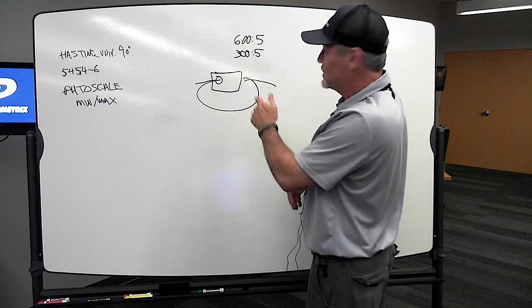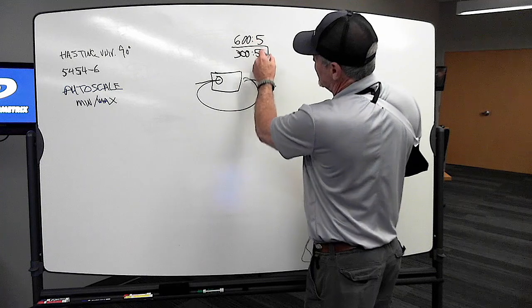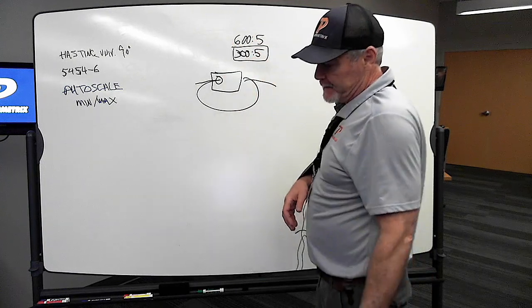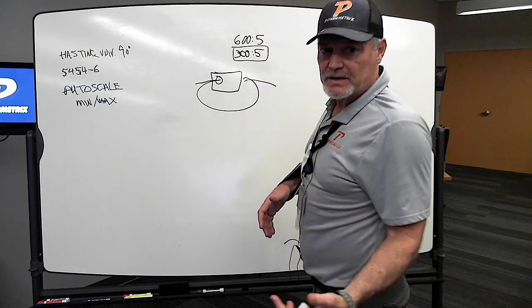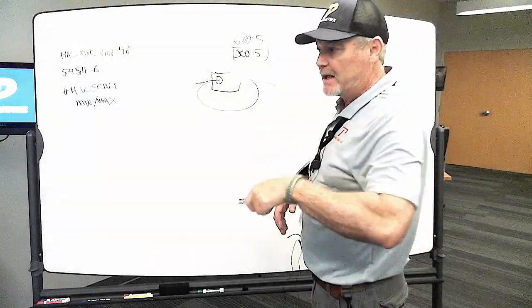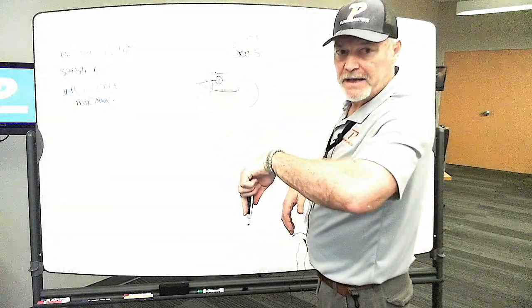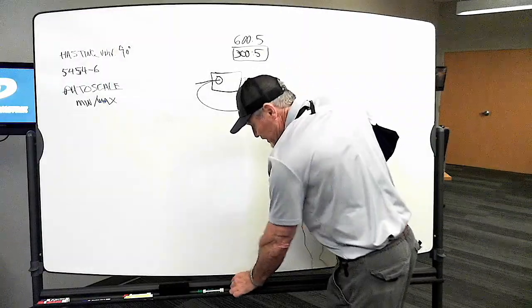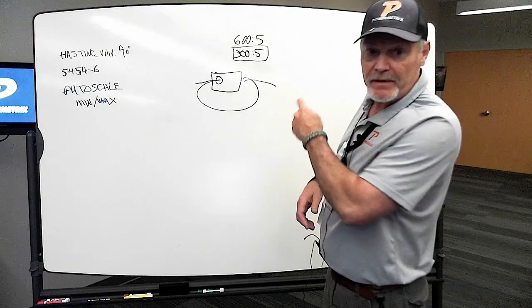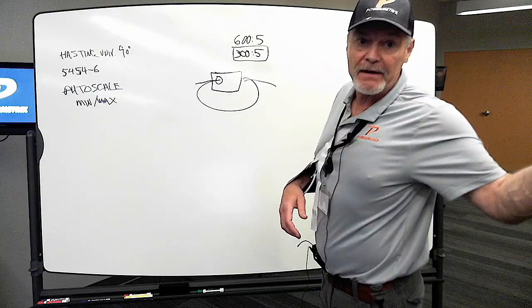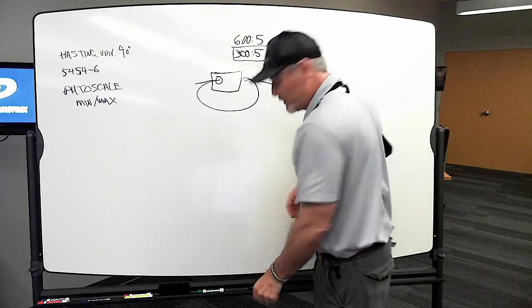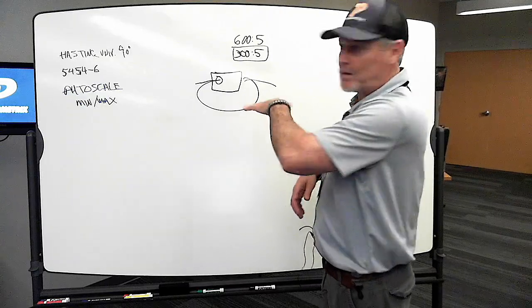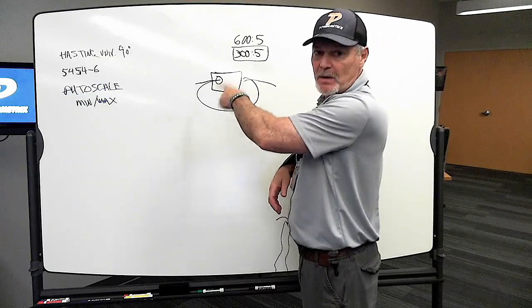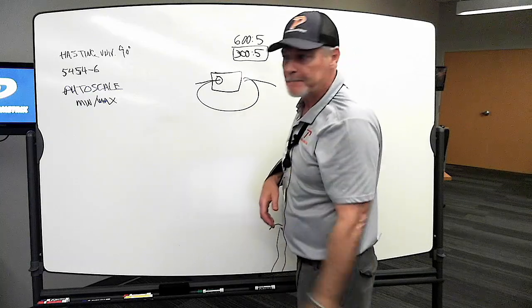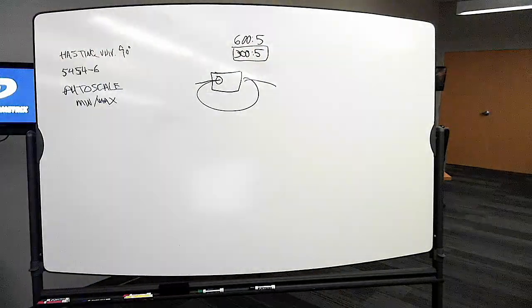It's not good. So what you've done is cutting, or ratio cutting, or cutting the ratio, or just cutting the CT - if you put more loops in it, knowing your loads are going to be down at the lower end, you'd want to pump more through there. Remember, we don't like to underload CTs. On that high C leg we've got that big 480 volt pump running over there, and with not much load on it, they still wanted to be able to read it. So they knew the amounts would be lower, so they went in and cut that ratio on that CT. Thanks, JP.